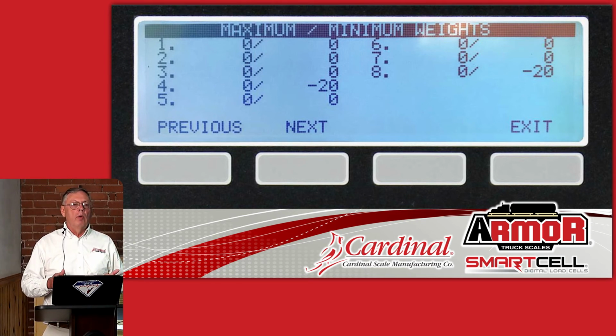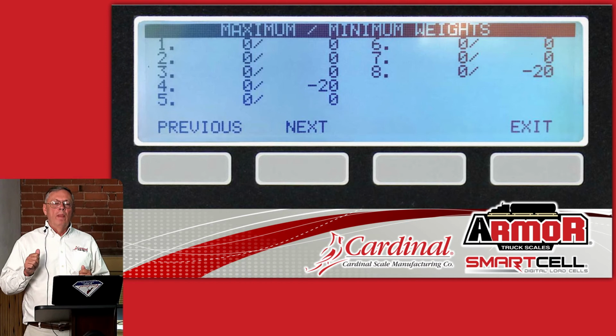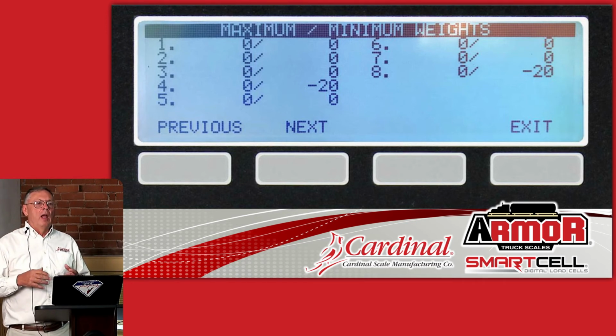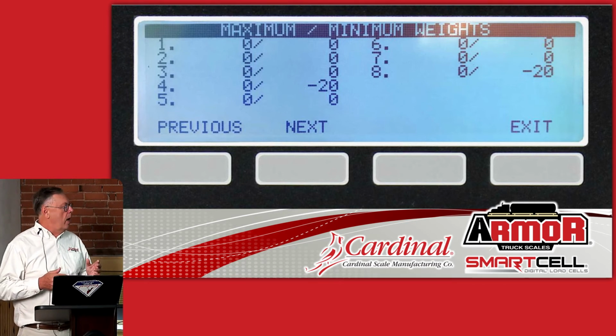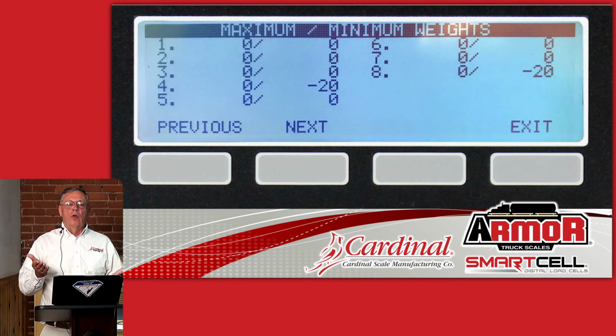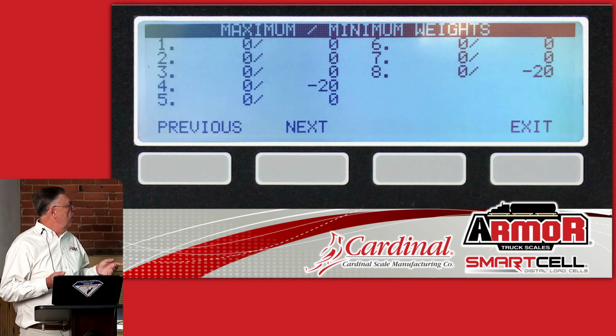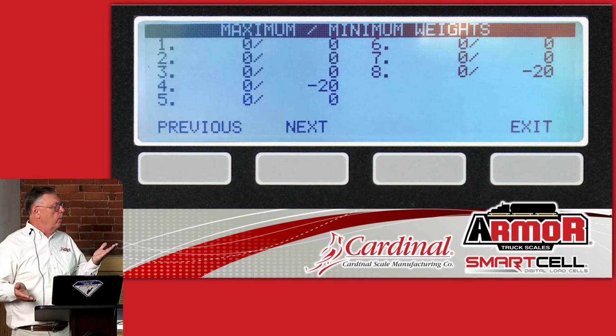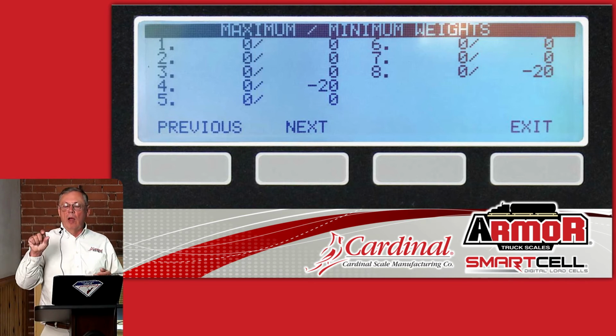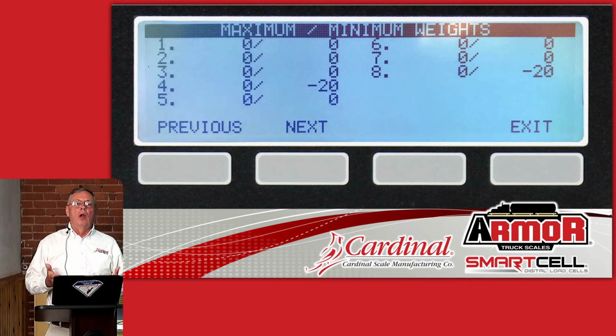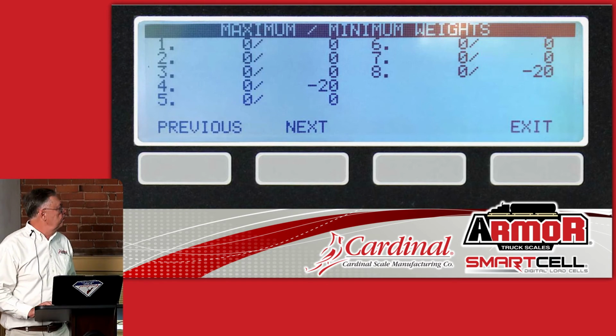With this system, we come to the second screen, hit the 0 button, and then after about 10 minutes, you want to look at it. And if there's a load cell that's drifting 1,000 pounds, it may show the maximum of 1,000, the minimum still at 0, and you know, hey, that one load cell right there is moving around on us. There's an issue with it right there. So it's very quick and easy. Because we're getting digital signals, we can tell which load cell's moving around on us.